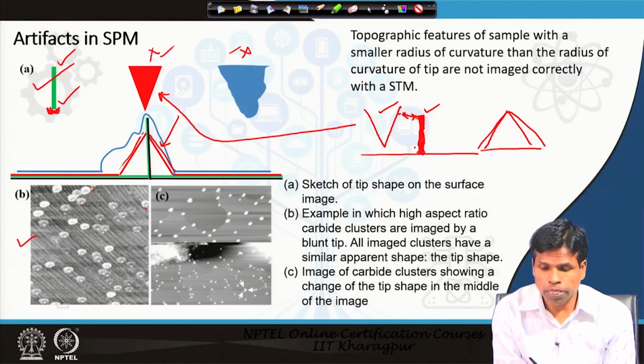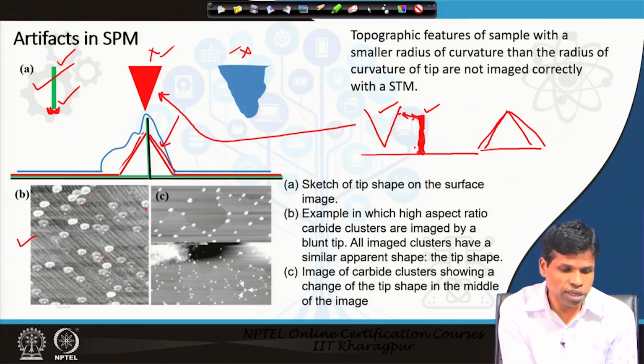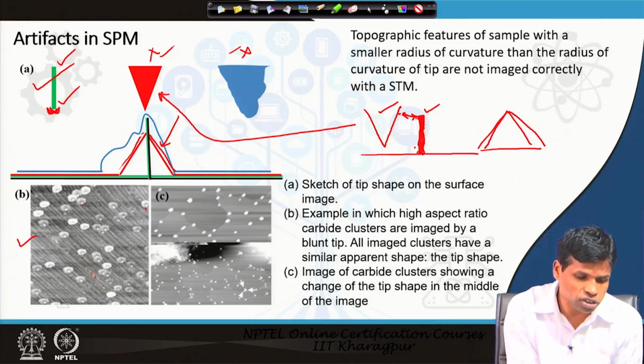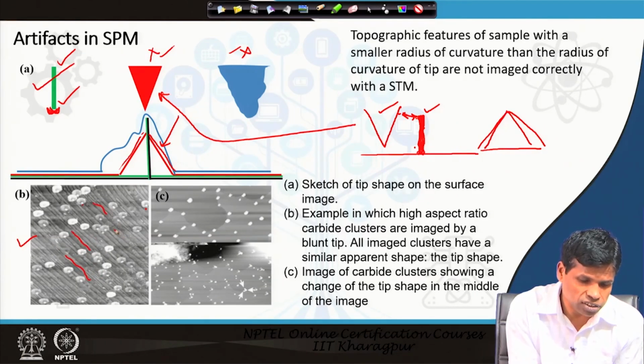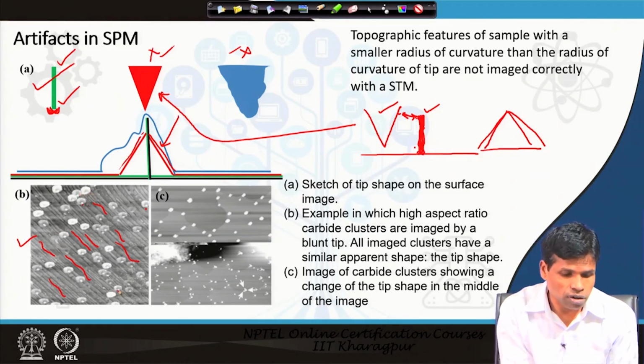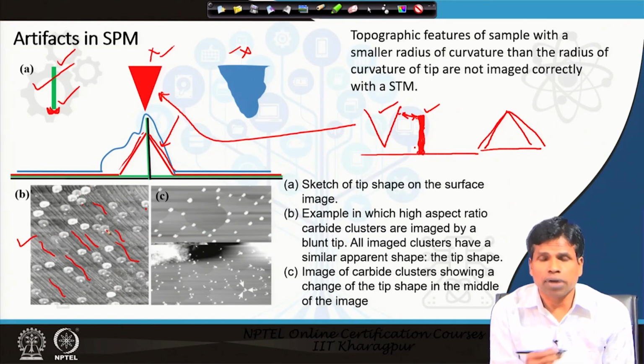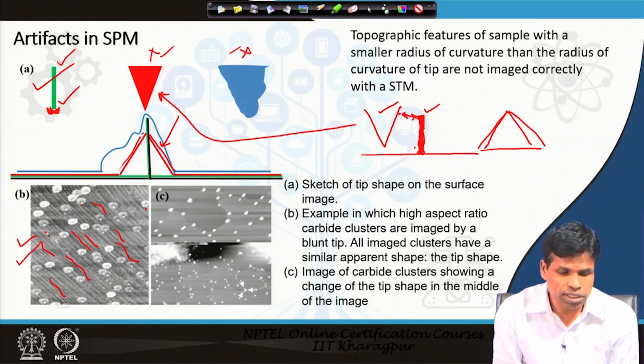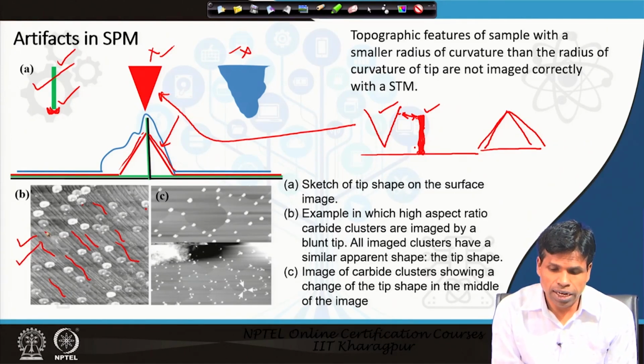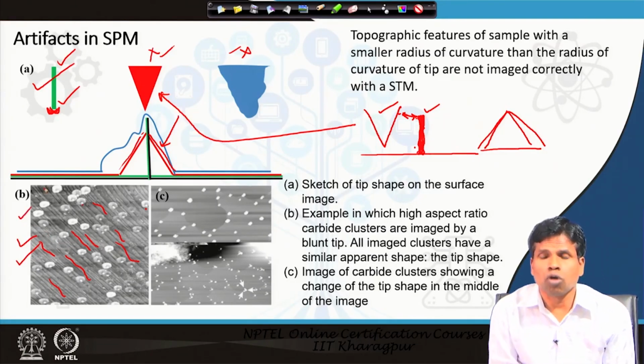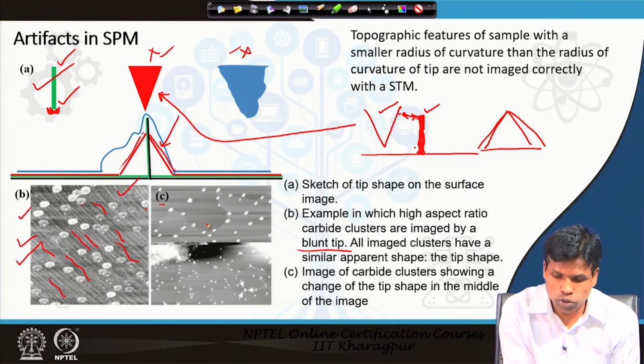and around that there is a halo, and these are carbide clusters. What we could see is that in addition to the carbide clusters, in the background there are one-dimensional directional features, and all these particles appear of similar shape with the middle portion brighter than the surrounding portion. So, this type of image indicates there is an artifact, something wrong with the tip. Here this image was collected with a blunt or not sharp tip, showing the image of the tip only, not the actual sample. In C, you could see those clusters of completely different shape.